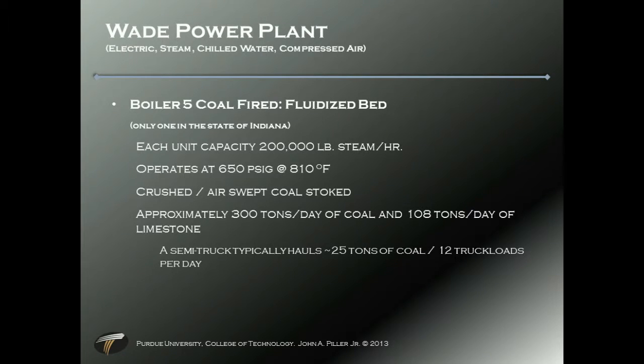Boiler 3 is an oil and gas fired. It can go by either fuel. Its capacity is also 200,000 pounds of steam. It operates at 650 psig, but at a lower temperature of 650 degrees Fahrenheit. It's designed for number 2 fuel oil. At full load, it'll take 39 gallons a minute.